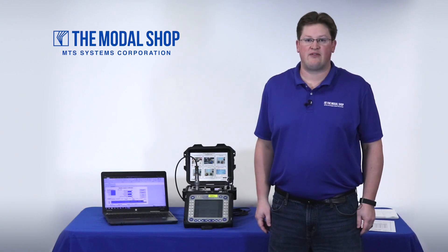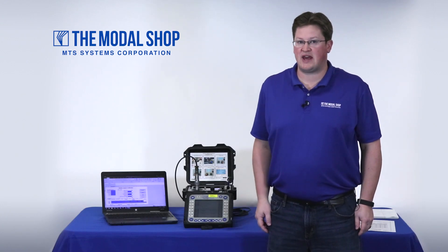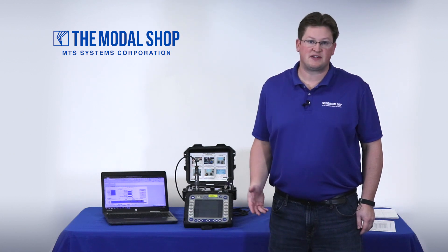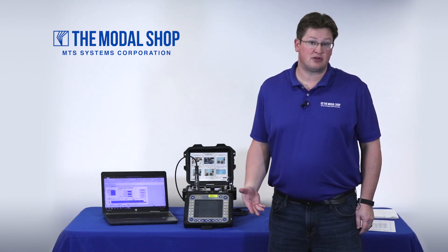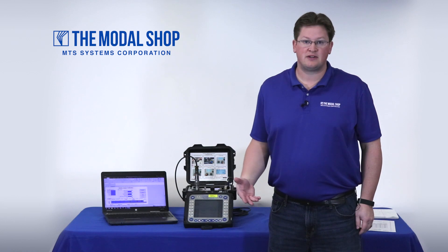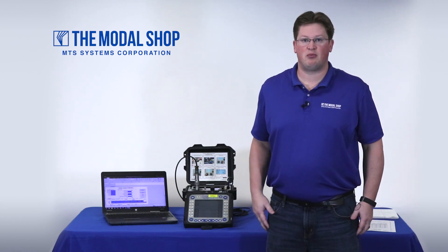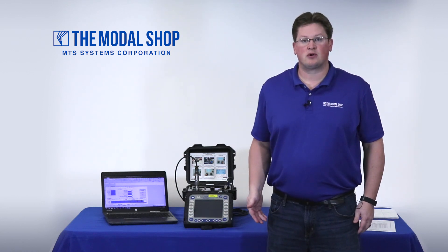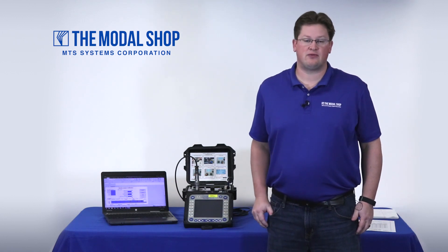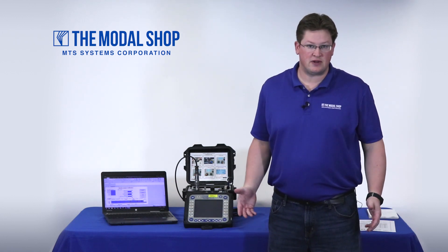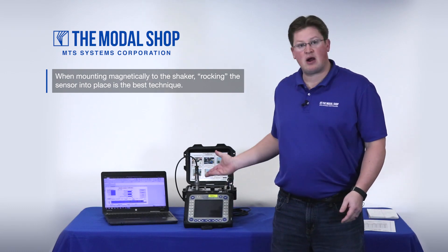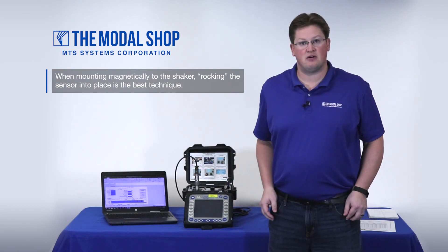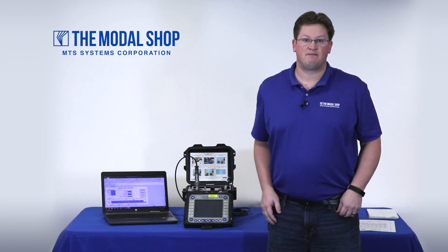Now that we have our 2130 vibration analyzer settings documented, as well as the sensitivity of our accelerometer supplied with the 2130 documented on our calibration report and tested, we're going to see how the 2130 performs in a linearity response test. And to do this, we can even mount the accelerometer magnetically, as you see here, or we can use a stud mount.